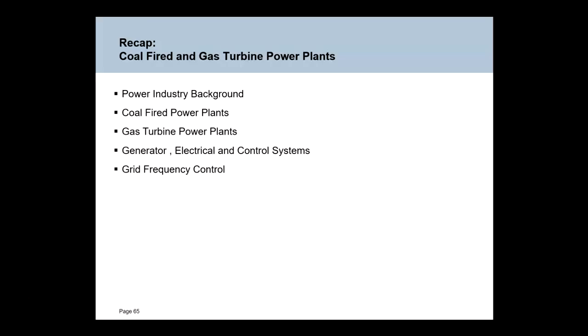So, again, just to recap, what did we cover? We talked about power industry background, about megawatts, megawatt hours, where are the coal plants, where are the gas turbine plants, what are the issues around the Australian industry, around the transmission network and so on. We talked about coal-fired power plants, how they go together, what the turbines look like, what the boilers look like, the gas cleaning and so on. We talked about gas turbine power plants, open cycle, combined cycle. We looked quickly at what does a generator look like, electrical and control systems, and we talked about grid frequency control. And we're spot on time.